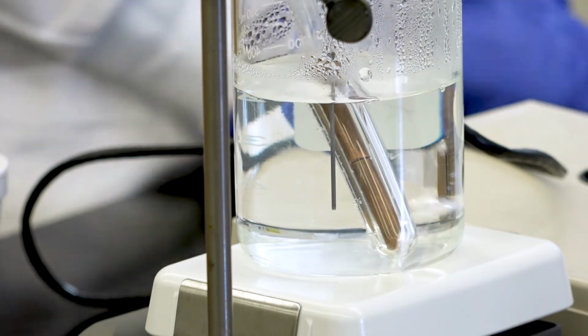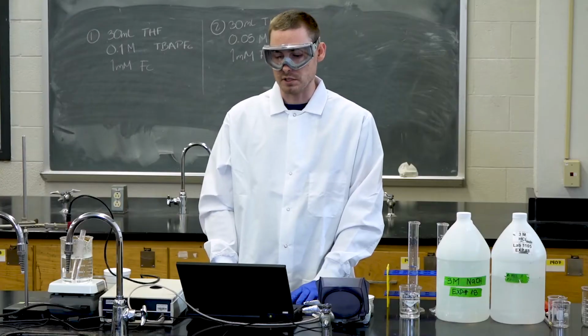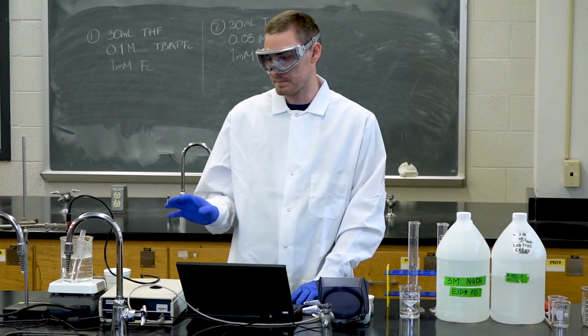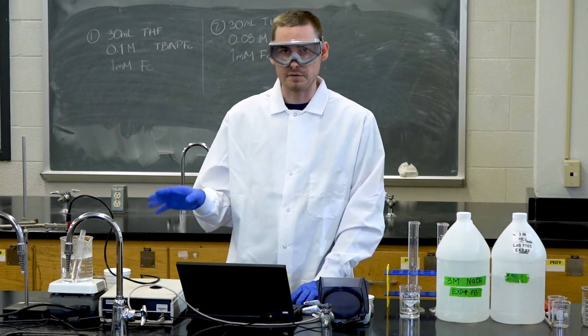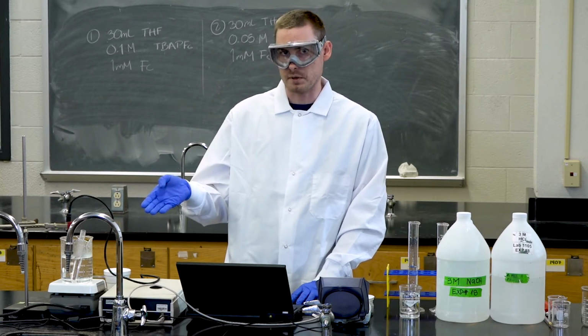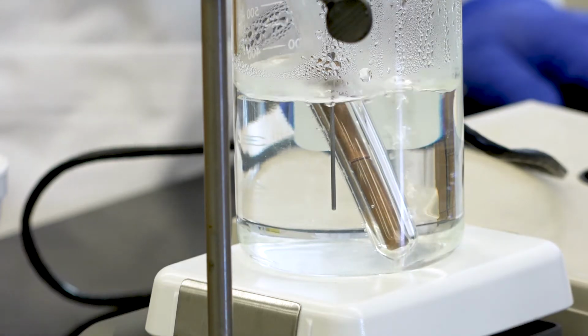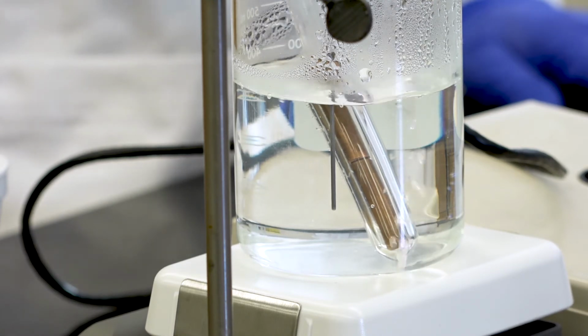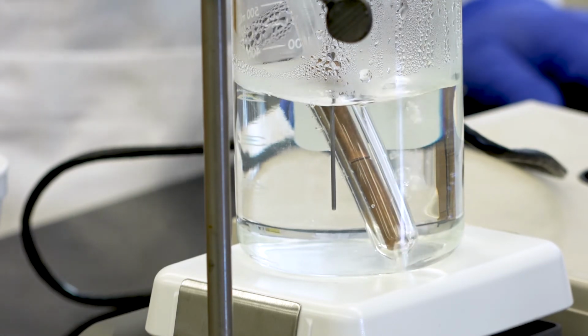It shows it's at 97 degrees Celsius, which is lower than you'd expect due to the elevation. And we're going to let it sit there for about 4 or 5 minutes so that the copper cylinders can come up to about 97 degrees Celsius before we start the calorimetry calibration.